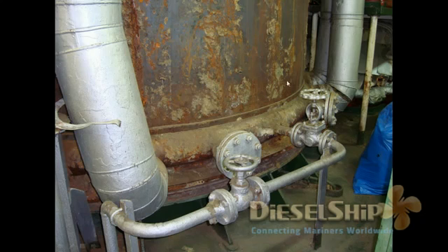What do you see over here? These come from the steam and water drum, and the downcomer brings the cold water to this water ring, and from the water ring you have tubes inside the boiler which generate steam and put it back to the steam drum. And what you see over here is the hand hole, and after emptying the boiler you can open this and clear the sludge out, and these are the blowdown valves. So we have two valves over here. These are the bottom blowdown valves.